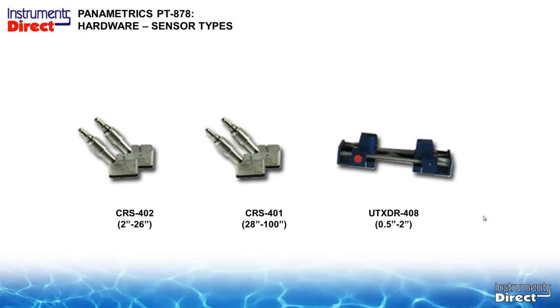Again, you can go to lower pipe applications if you say have heavier solids or poorer pipe wall conditions. And then the small pipe sensors, the 408 is on its own little track, which is a nice small footprint. Off the top of my head, it's only got like a 6 or 8 inch footprint, so it's really good if you're in an HVAC application close to the coil that you don't have a lot of straight run of pipe. So you need a smaller footprint there.